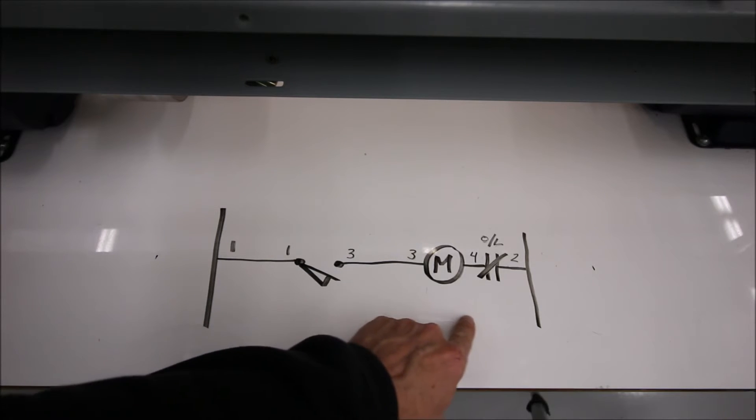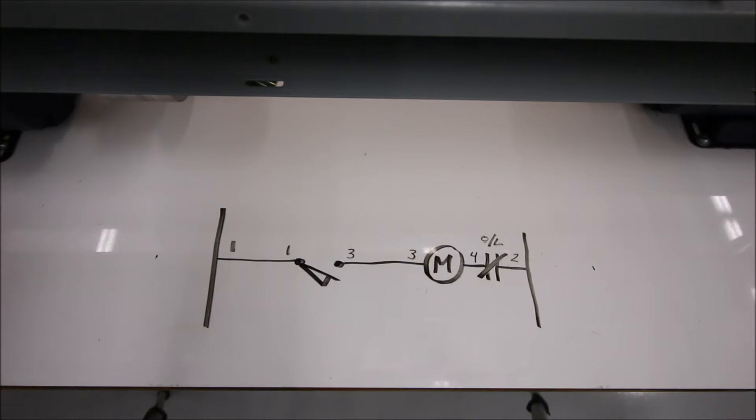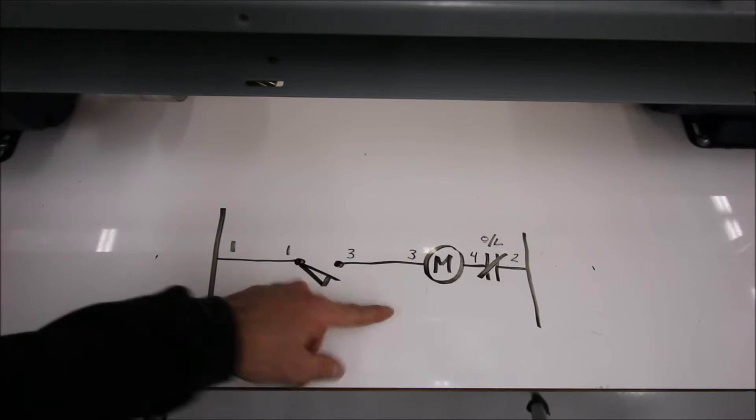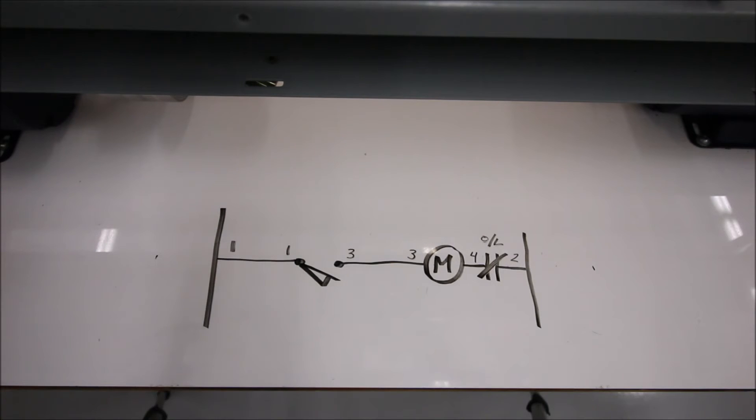Now this one is going to provide two-wire control in that when I close this switch, the motor is going to turn on. When I open that switch, then the motor is going to turn off. There will be no way to maintain that contactor being on. Let's take a look at how it's wired.